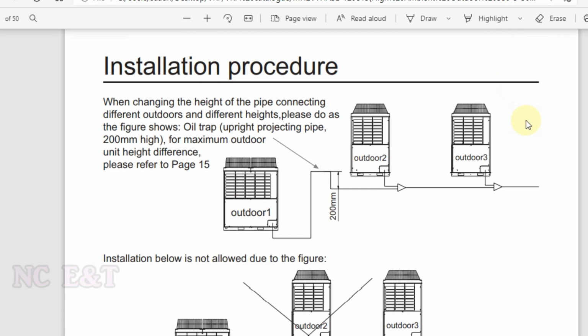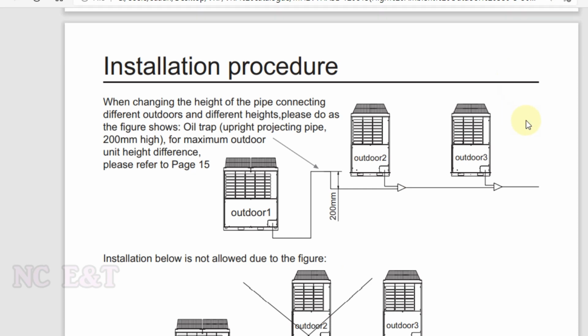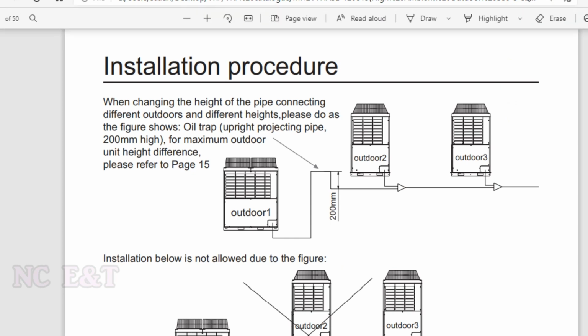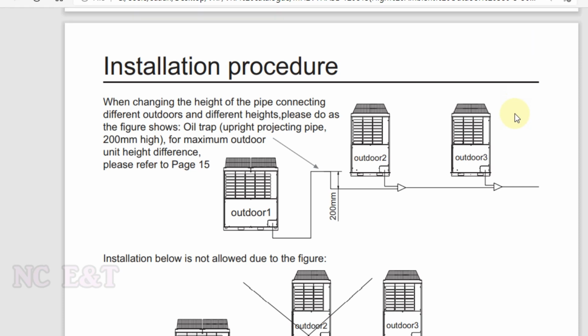If we have more than one outdoor unit in a circuit and different outdoor units are at different heights, we need to provide an oil trap between the different heights of outdoor units when we connect the piping. So in the piping connecting the different height outdoor units, we need to provide the oil trap, and it should be upward, and the minimum height of this trap should be 20 centimeters.